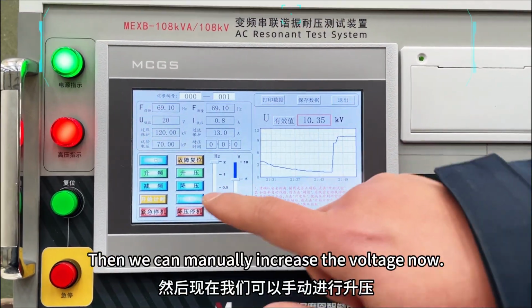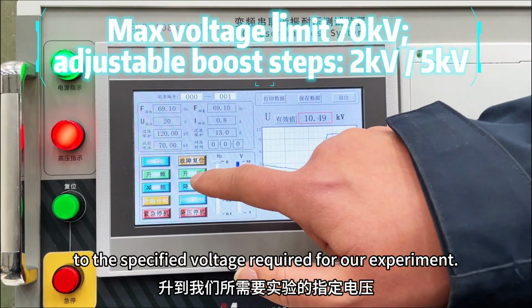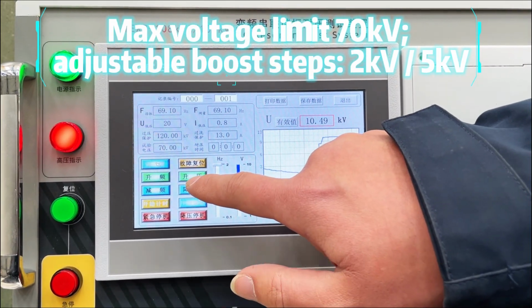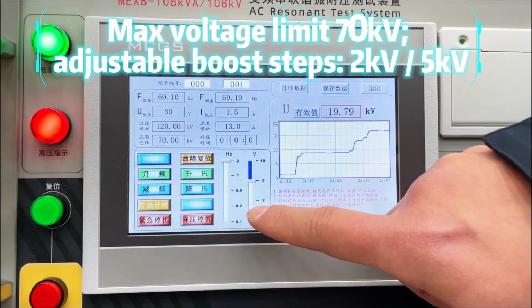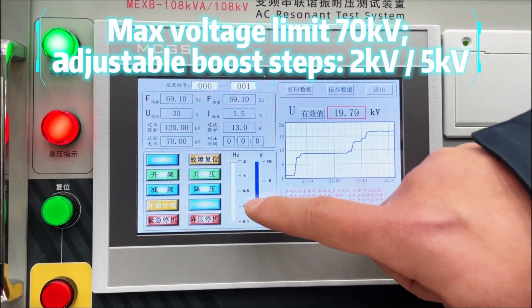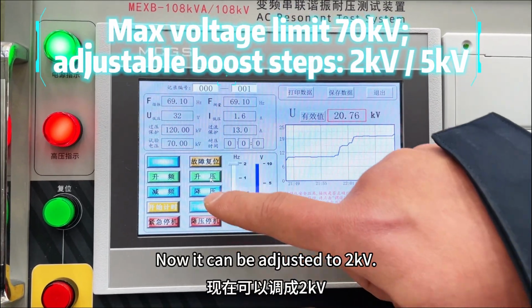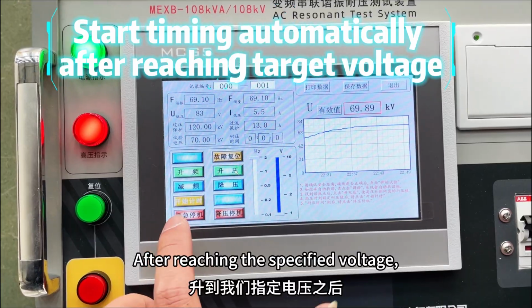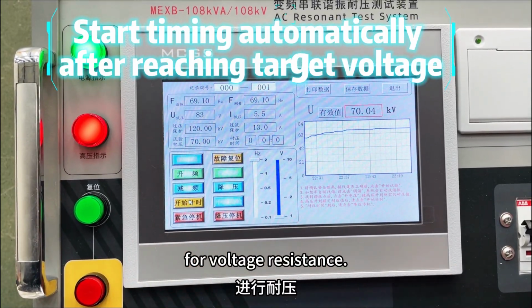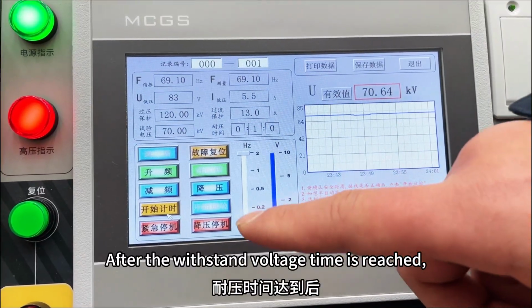Then we can manually increase the voltage now to the specified voltage required for our experiment. We can adjust the boost gear here. It was 5000 volts just now, and now it can be adjusted to 2000 volts. After reaching the specified voltage, click to start timing for voltage resistance.